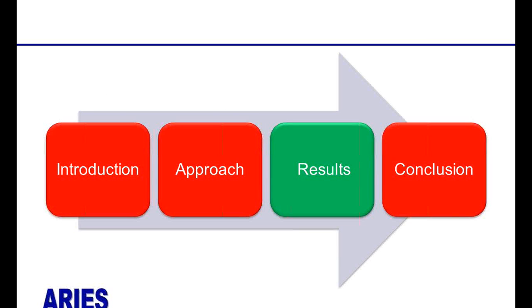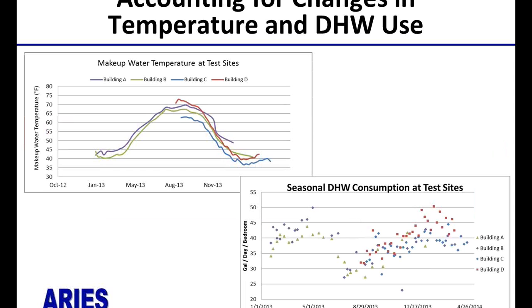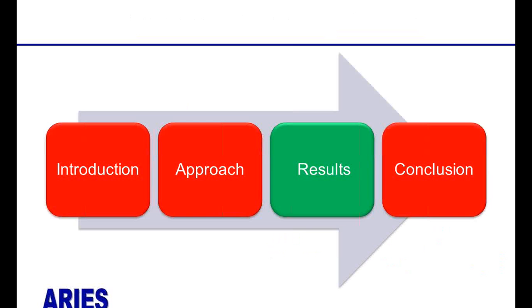Can you go back one, actually? Sorry. So in order to account for this when comparing the baseline to the continuous across these 4 seasons and to the test controls, we wanted to make sure we were measuring fuel savings attributed to the controls and not to these effects. So we normalized the boiler runtime data for 3 parameters: the gallons of DHW consumed per day, the incoming cold water temperature from the city mains, and also for the DHW supply temperature that was being sent out to the building occupant.